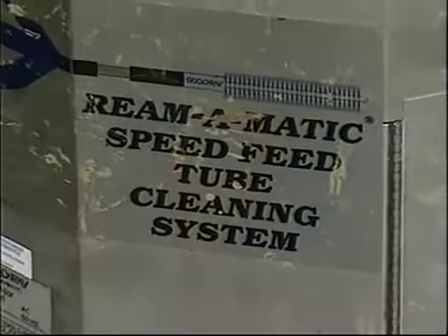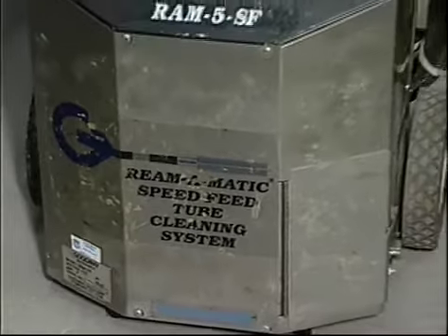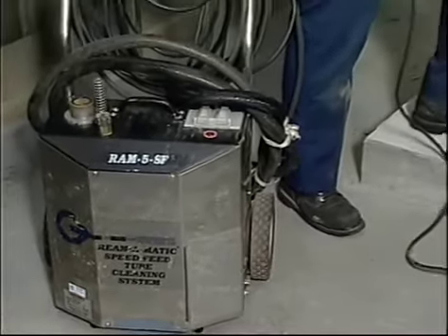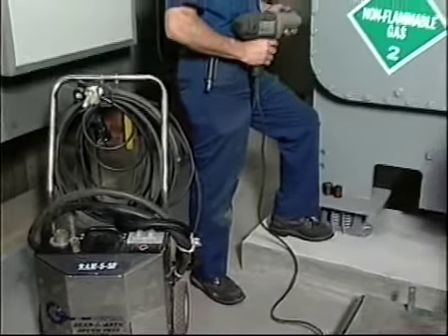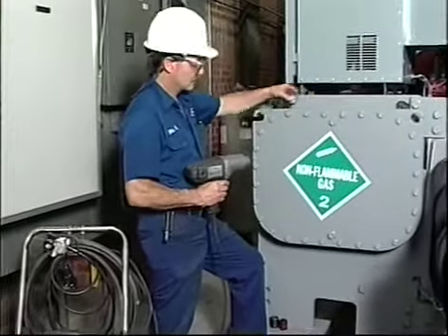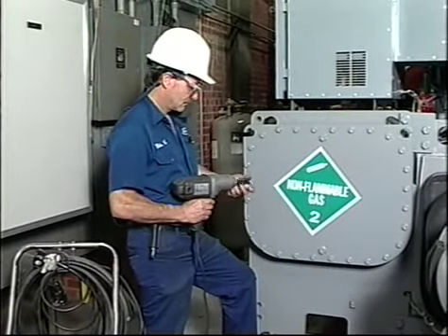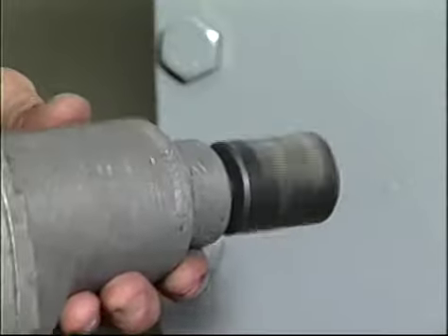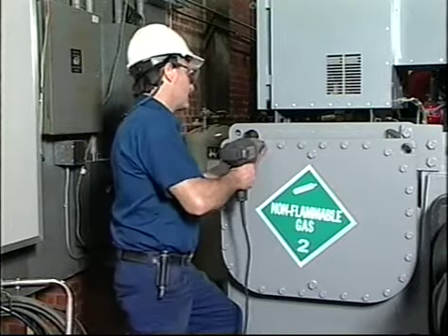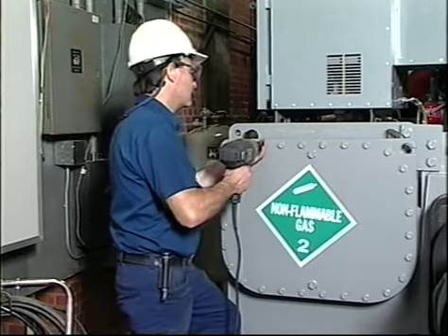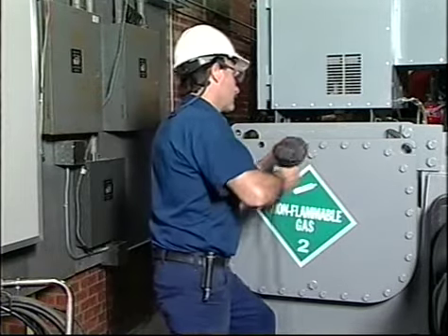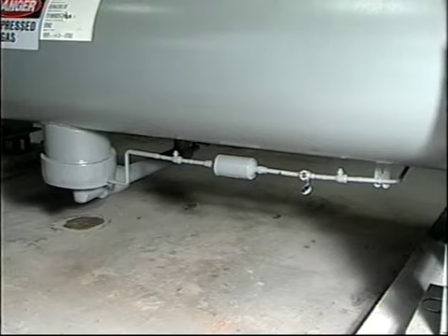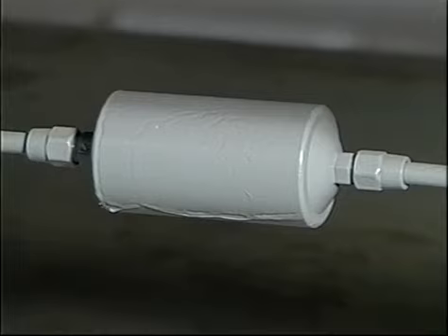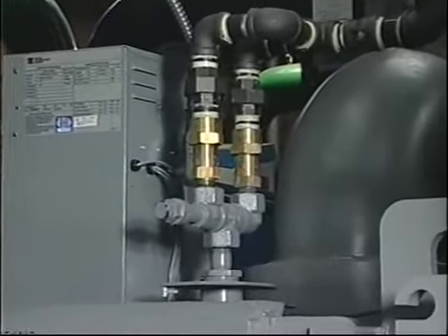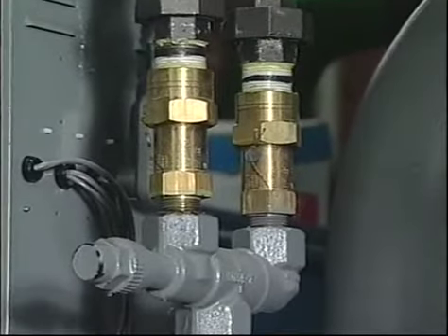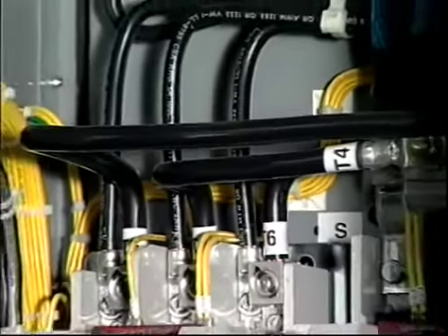The condenser tube should be cleaned and the cooler tube should be cleaned and inspected after the first year of operation. Because the chilled water is a closed circuit, the cooler tubes normally will not need cleaning every year, but the first-year inspection will give the technician a chance to see if the water treatment is adequate and to determine a schedule for future cleaning. The condenser temperature sensors should also be checked for scaling and fouling and cleaned if necessary. Other annual maintenance chores include changing the oil reclaim filter in the cooler scavenging line and inspecting relief valves for signs of corrosion, dirt, or leakage. Another important item to check is the compressor motor starter.